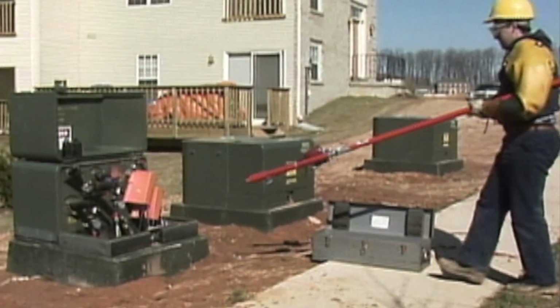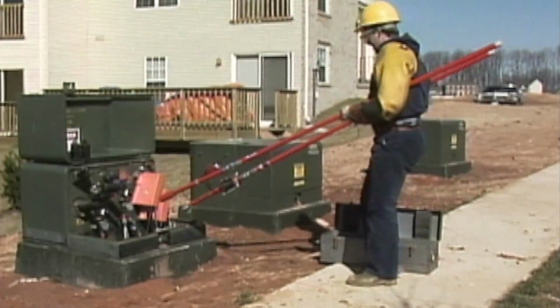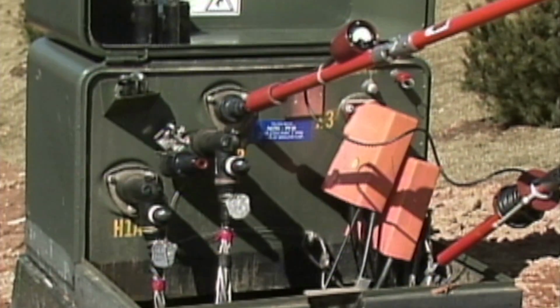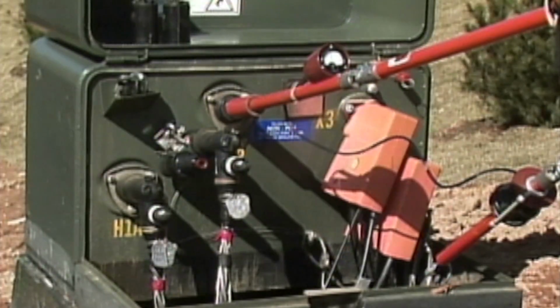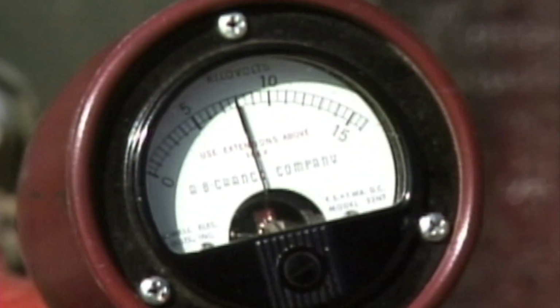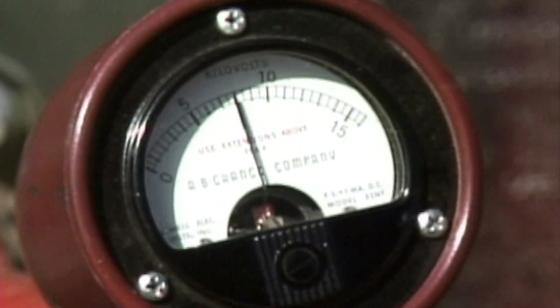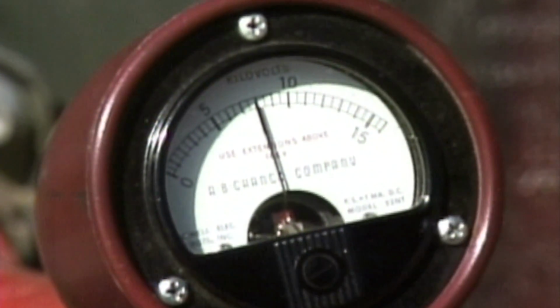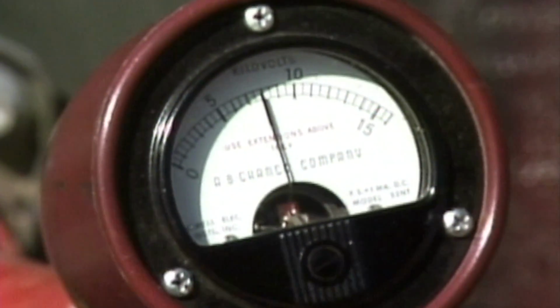As with the stethoscope, the first thing the lineman does is check the phasing tool to make sure that it's operating properly. To do this, he touches one of the test probes to the transformer ground and places the other probe into the energized transformer bushing. He gets a normal phase to ground reading. This verifies that the meter is functioning properly.